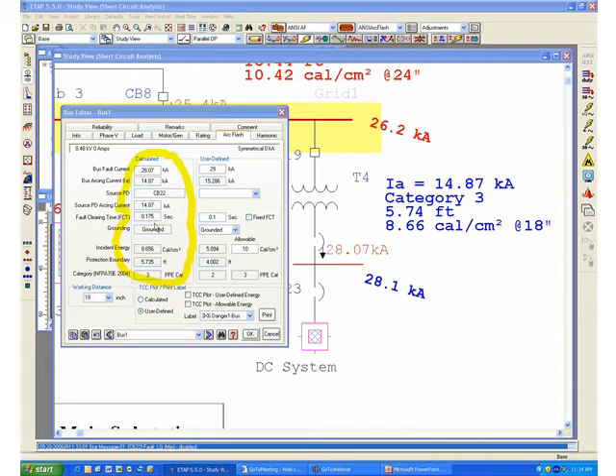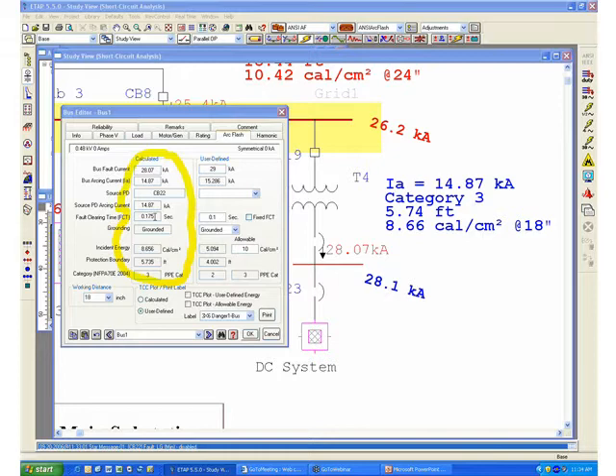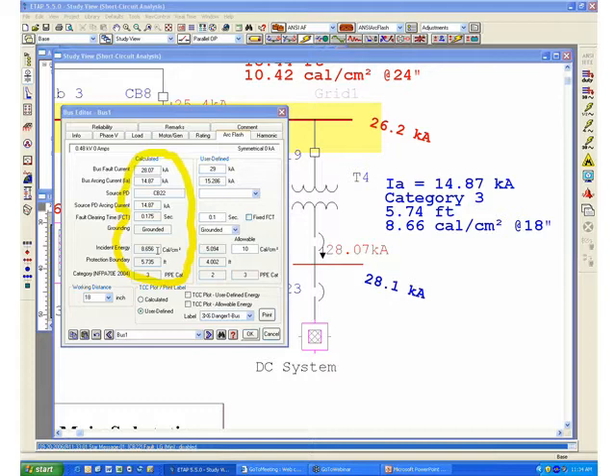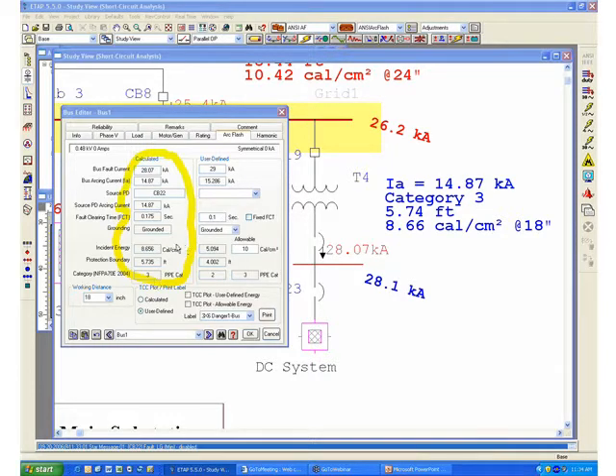The current and full clearing time or response time of that low voltage circuit breaker is approximately 175 milliseconds or 0.175 seconds. The system has been determined to be grounded, and the program will automatically populate the incident energy, flash protection boundary, and the category level.